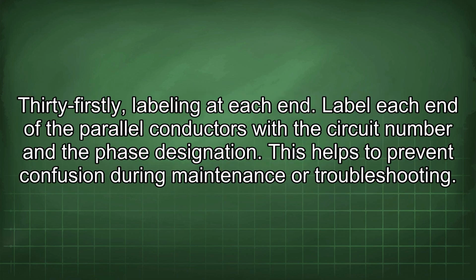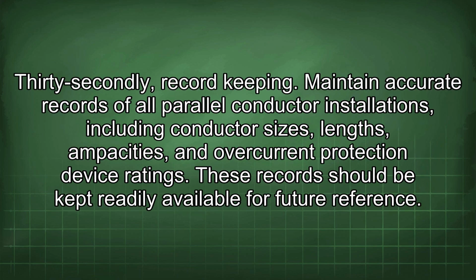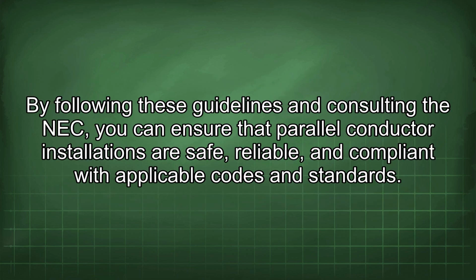31st, labeling at each end. Label each end of the parallel conductors with the circuit number and the phase designation. This helps to prevent confusion during maintenance or troubleshooting. 32nd, record keeping. Maintain accurate records of all parallel conductor installations, including conductor sizes, lengths, ampacities, and overcurrent protection device ratings. These records should be kept readily available for future reference. By following these guidelines and consulting the NEC, you can ensure that parallel conductor installations are safe, reliable, and compliant with applicable codes and standards.